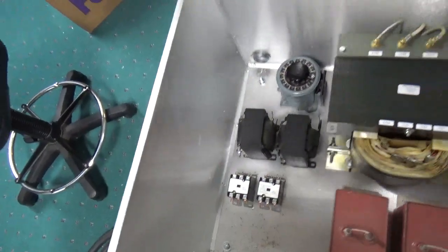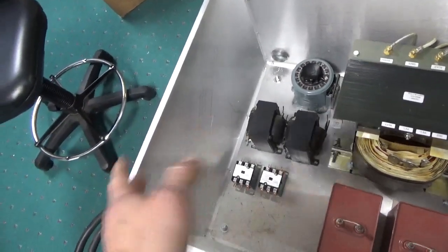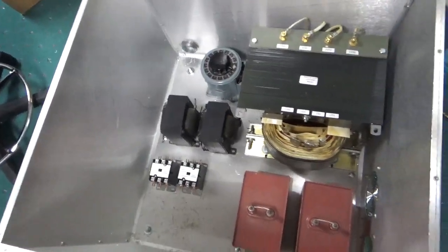It'll have a pressure interlock, so if it wasn't positioned right or it lost the blower - because this will be in a different room away from him - it'll shut the plate down, shut the filament, it'll shut everything off.